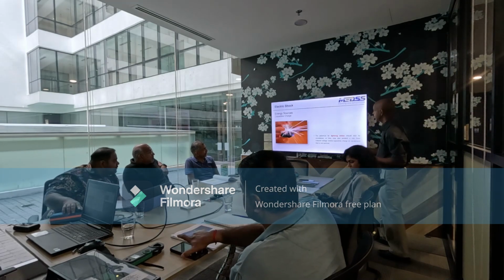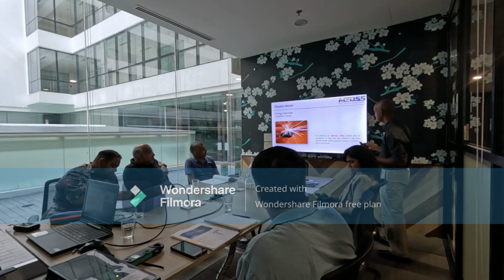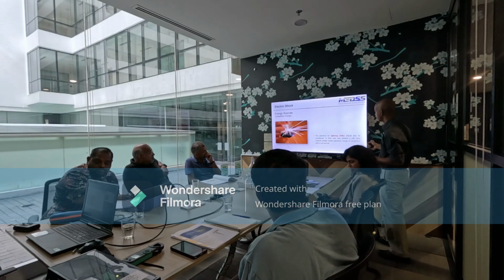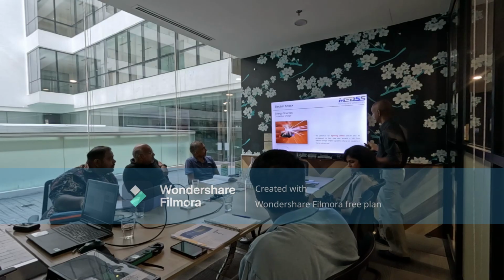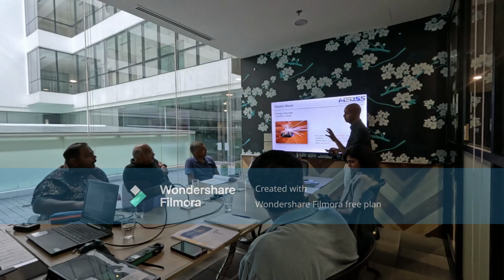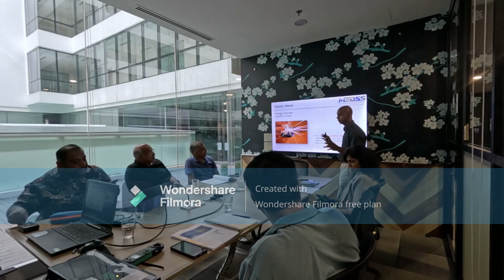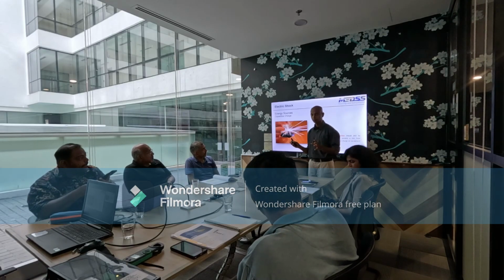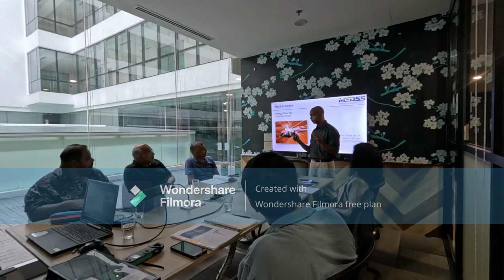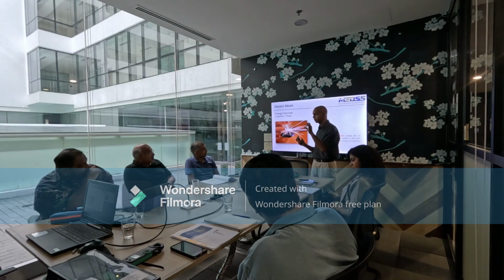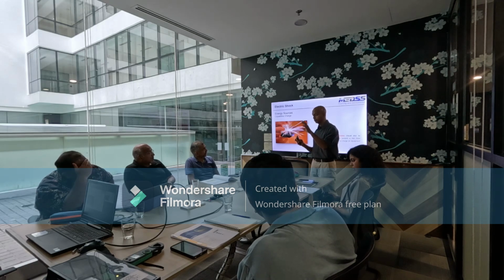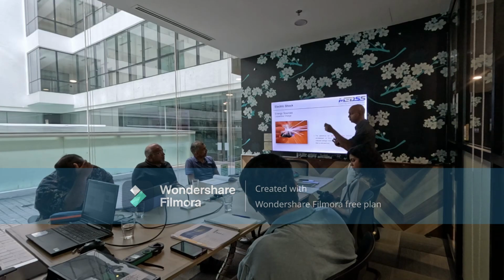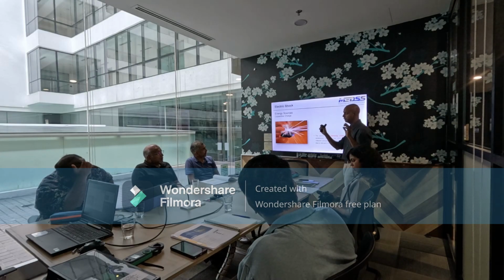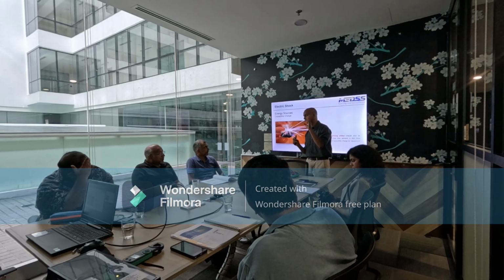An energy source, potential lightning strike should also be considered as it presents a risk from induced voltage or capacitive charge on the equipment. Talking about capacitive charge, those in the switchboard business know your bus bars are huge conductors. So when you switch off your switchboard supply, if you don't discharge it, your bus bar actually stores energy. That's the capacitance energy, so your bus bar itself is a capacitance.